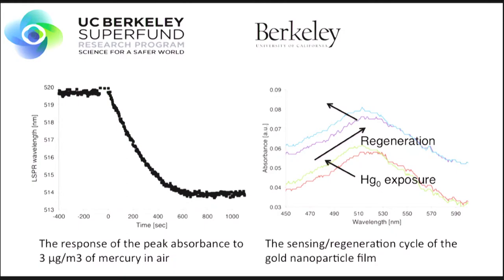The rate of the peak shift is proportional to the concentration of mercury in the sample. We've shown this and we expect this, because the collection of mercury by the gold film is diffusion limited, and diffusion is driven by a concentration gradient and is proportional to the concentration of your diffusing species.